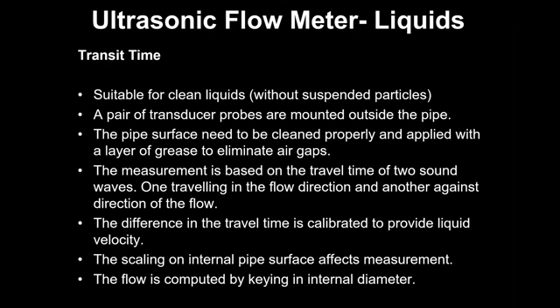Now, one needs to be careful about this because, as I said, readings can be erroneous. As such, the signal received back is very small, less than a percent of what you are emitting. If there is an error in that, the reading cannot be correct. So we have to ensure that we are following the method correctly, installing the meter correctly, and that the pipe is cleaned.